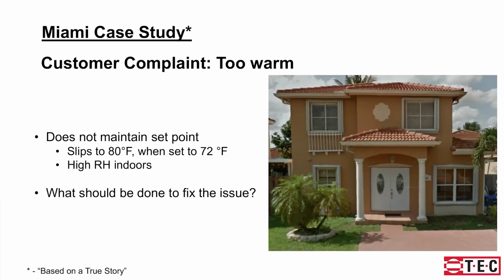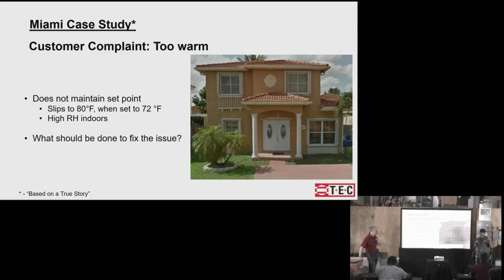But the complaint was a common one in Miami. Hey, it's just too warm everywhere in the house. This house is just not comfortable when it gets hot. It's running all the time, and it's not comfortable. And so it's not maintaining a set point. It's going to 80 when I have my set point at 72. I've got very high relative humidity indoors, and I can't figure out what's going on. Okay, and so Steve's going to step you through some of the steps to diagnose that.